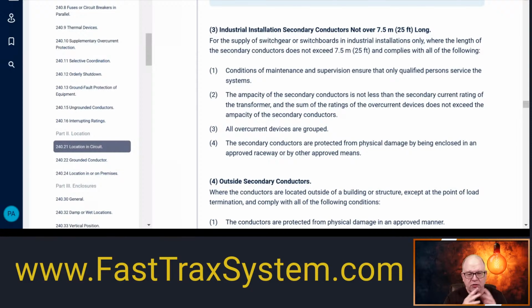So if you got a transformer, it's got no protection on it, and you're required to have that protection. Let's say you're using primary and secondary protection in 450.3, okay? Then if that's the case, you have to protect that transformer secondary. Well, if you have to have primary and secondary protection, and you also are using that allowance for protecting the transformer, now we have to protect these conductors. And the whole point of the secondary conductor rule, see how easy it is to do that, is to limit it. If you could come off of that transformer with the 400 amp rating and run it unlimited, then what would be the purpose? What would be the point of these secondary conductor protection rules?